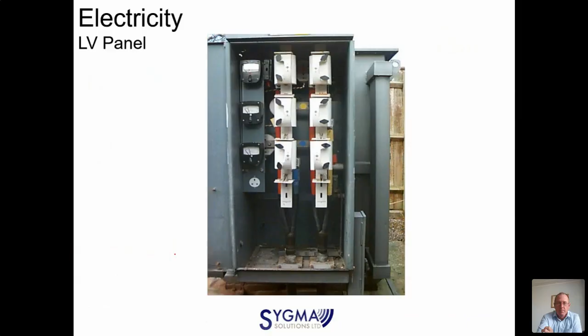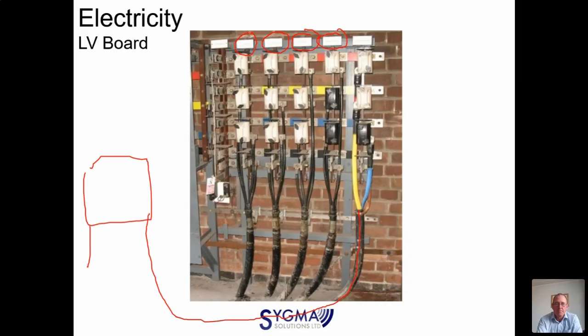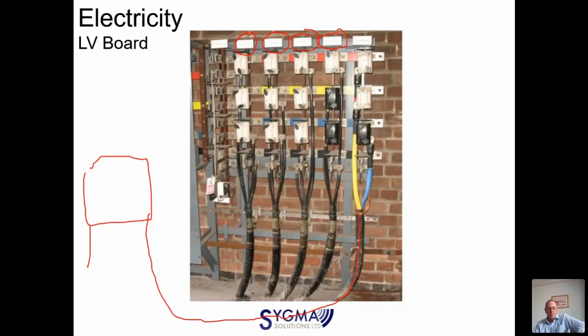So going back to this same picture you saw earlier on - the transformer, 11 kV, out here somewhere, may well be in the same building, and then that's your LV supply coming in from the transformer. If you do find yourself in a sub, this will tell you where these cables are going. Again, I wouldn't take it as gospel, but it should be relatively accurate, so it'll give you a clue as to where things are supposed to be going if you find yourself in an LV distribution substation, which is increasingly probably very unlikely nowadays, unless you're working on behalf of the power companies.